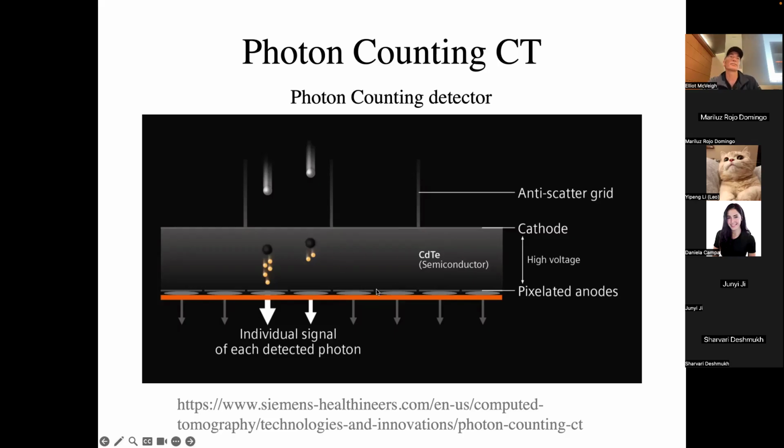So you can imagine here you don't see septa, for one thing, because you don't need to worry about the light spreading through the entire detector or crystal. What happens is the X-ray is detected, these charges are created, and they just go straight to the diode here. The nice thing about not having the septa is your efficiency goes up, because you don't have things dividing your detector elements. And you get a much higher precision detection as to where that occurs.